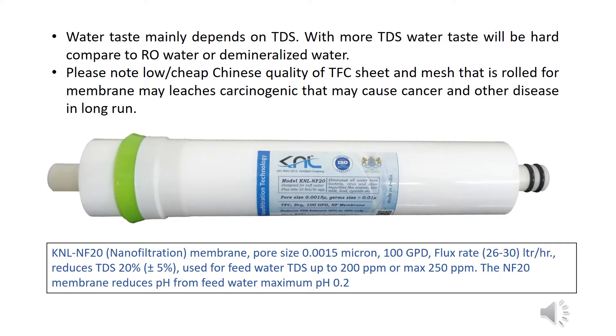KNL NF-20 nanofiltration membrane: pore size 0.0015 micron, 100 GPD, flux rate 26 to 30 liters per hour, reduces TDS by 20% ±5%. Used for feed water TDS up to 200 ppm or max 250 ppm. The NF-20 membrane reduces pH from feed water by a maximum of 0.2.